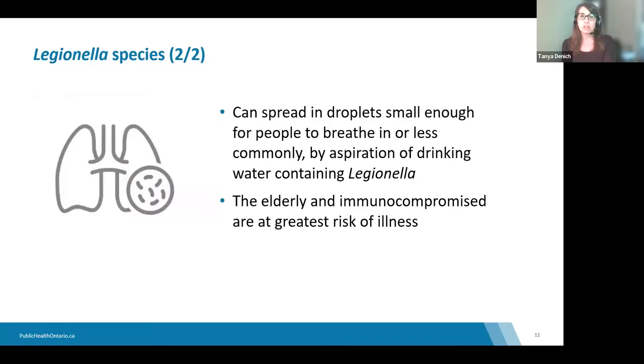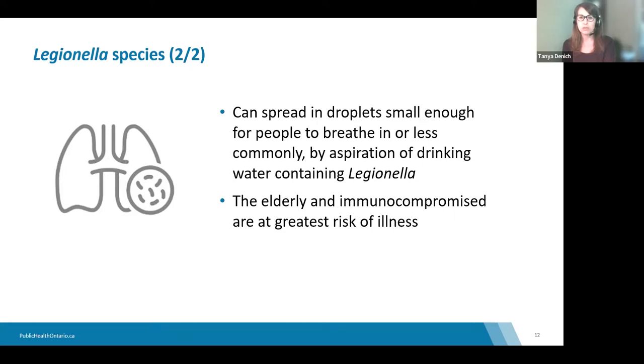Legionella can be spread in droplets small enough for people to breathe in, or less commonly by aspiration of drinking water containing Legionella. The elderly and immunocompromised are at greatest risk. Legionella thrives in water temperatures between 20 and 40 degrees Celsius, so it's important to keep cold water cold and hot water hot to prevent ideal conditions for Legionella growth.